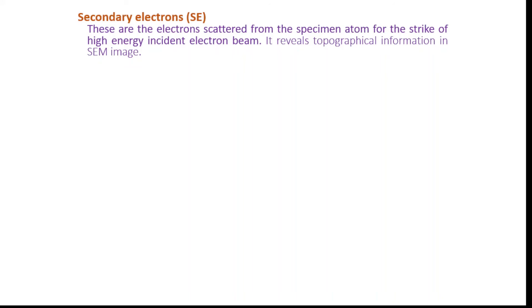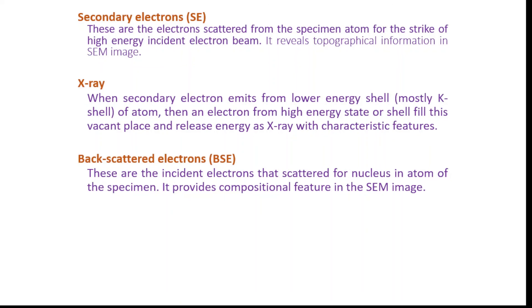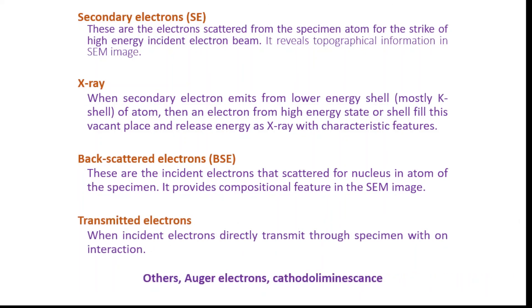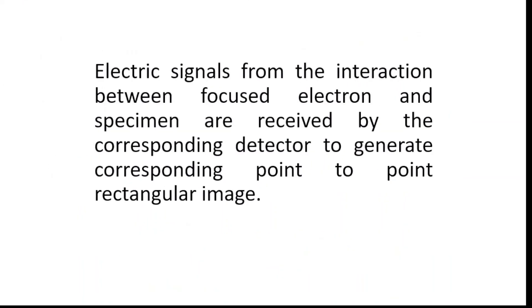Secondary electrons are generated by the strike of the high energy electron beam scattered from atoms of the sample. They reveal topographical information — meaning the surface morphology, surface roughness, or surface structure of the specimen. X-rays generated from this process allow analysis of the elemental composition of the sample. Backscattered electrons are high energy electrons repelled by the nucleus of the atom and provide compositional features in the SEM image. Other phenomena like Auger electrons and cathodoluminescence emissions also occur and provide additional information about the samples. The electric signals from these interactions are received by corresponding detectors, generating a corresponding point-to-point rectangular image.